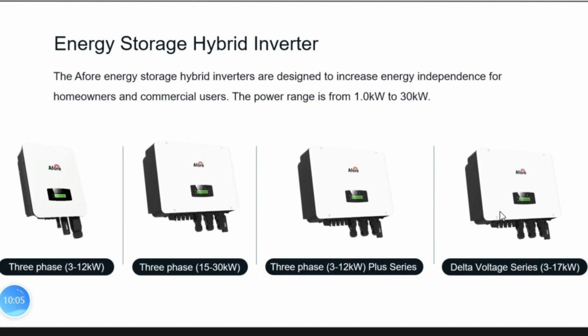Start from 3 kilowatts to 20 kilowatts, to 30 kilowatts. In the first part, 3-phase, 3 to 12 kilowatts, normal version. Why do we call it normal version? Because in this industry, most 3-phase hybrid inverters' charge and discharge current is about 35 amps. So that is the normal version.